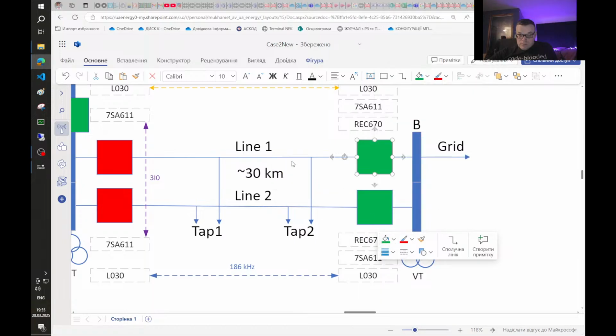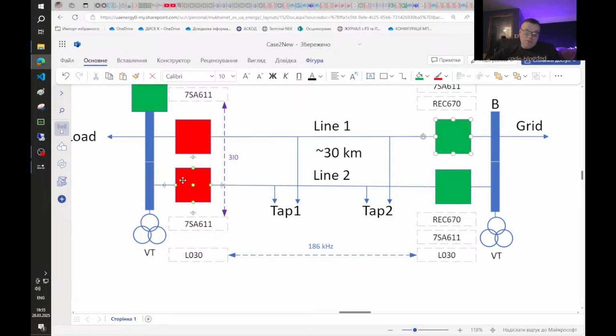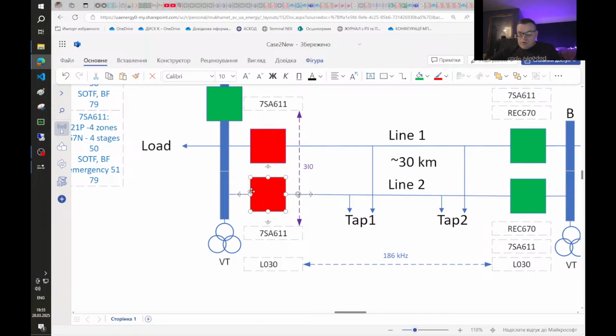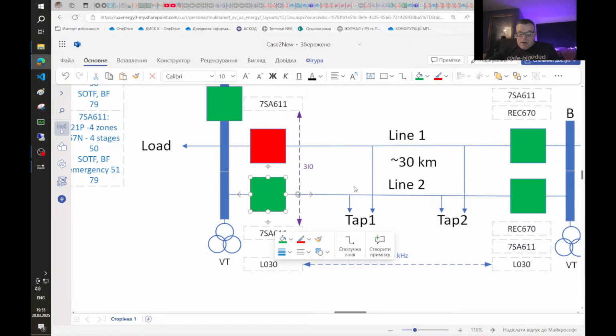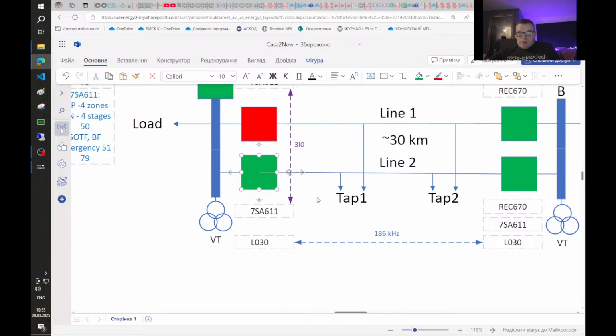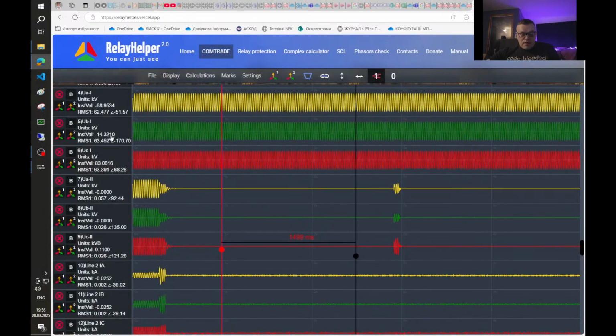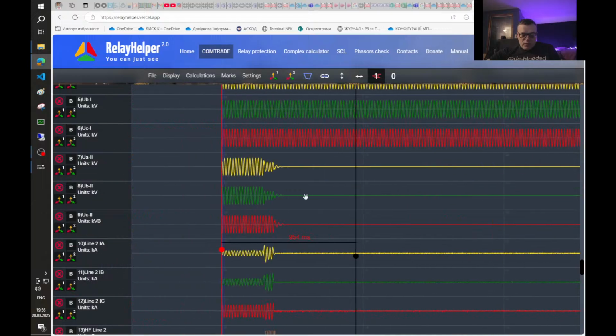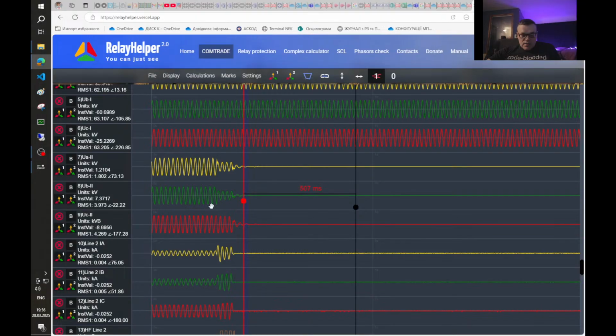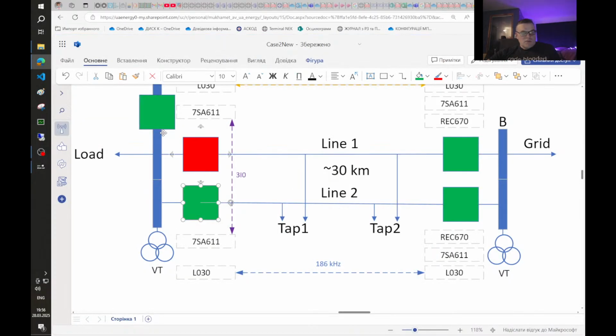So let's, but also currents were big enough to initiate trip on that side of the second line. So from this side, the circuit breaker was opened by the phase differential protection. But in this case, when three circuit breakers were opened, we lose voltage on the bus bar. So there is no need for any protection, and there are no parameters for protection to trip this circuit breaker.